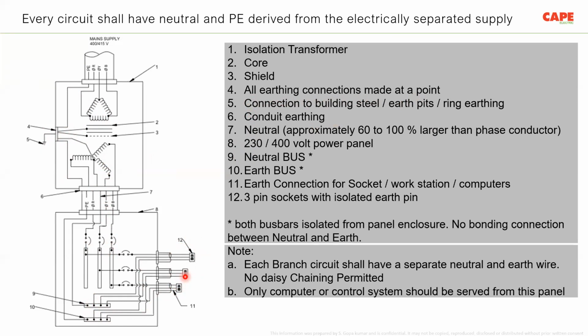But as I said, in about 50-60% of places there are violations. Of course, the designer makes a design like this, but the contractor, while installing, in order to save the cost of a few pieces of wire, makes a daisy chain. This is the reason. The testings mentioned in IS 732, I always used to tell, there are 18 inspection points and 10 testings. These are very important, so that in case of any mistakes, especially these loopings, we can easily find them and rectify those defects.